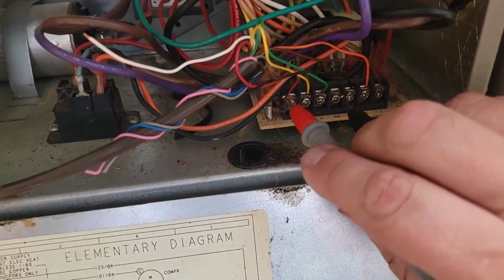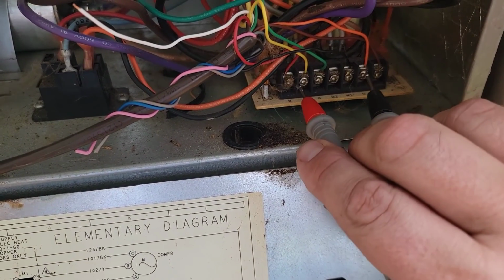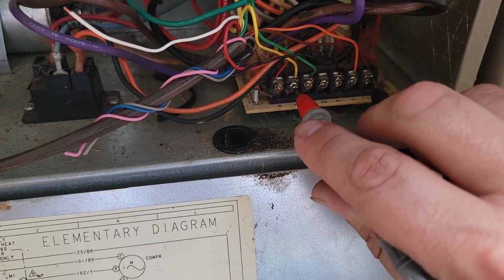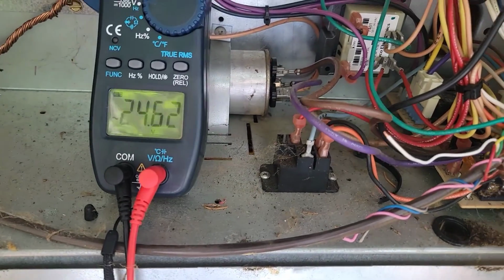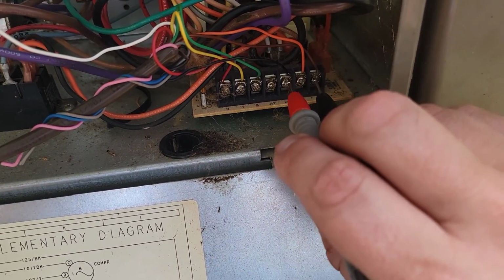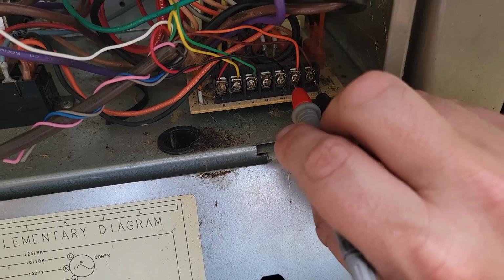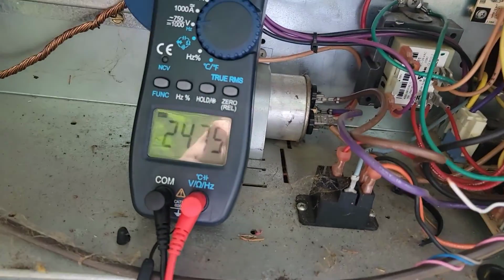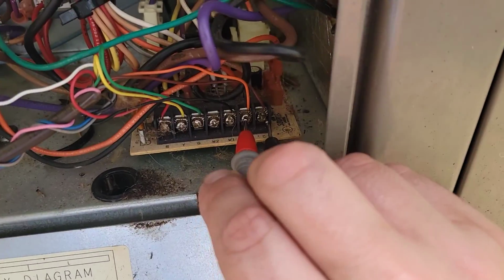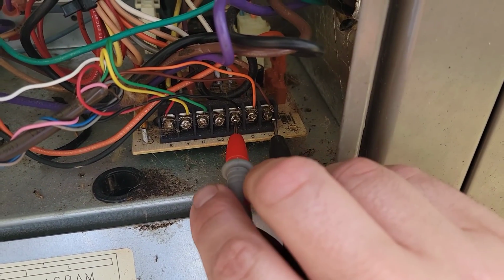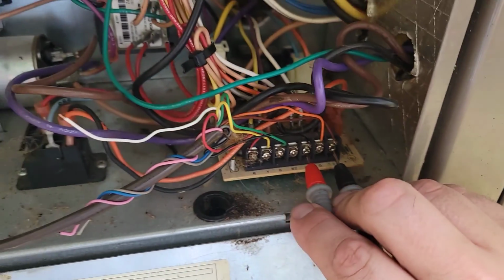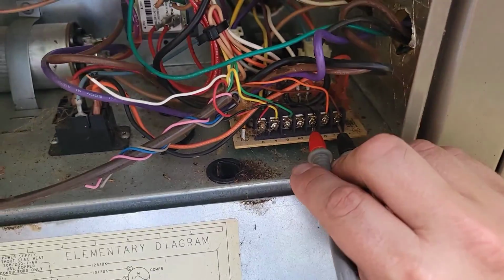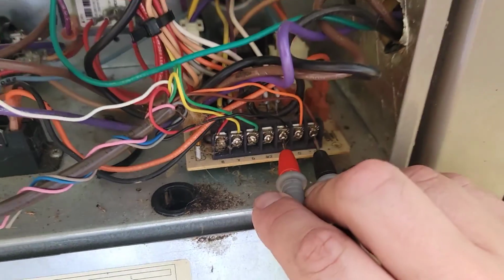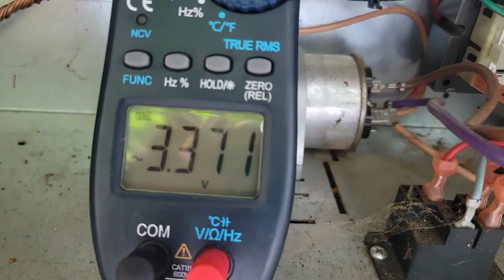The unit's back on. We got the meter set to volts. It's in the cooling operation, so of course we should have power between C and Y. Of course we do, 24 volts. We should also have power to the orange, which is the reversing valve. It should be energized and cooling, so yes, we do. And we should not have volts between C and W now. So we're using the black wire instead of the white wire. I took it off at the thermostat and off of this board where the terminals are. And I'm using the black instead.